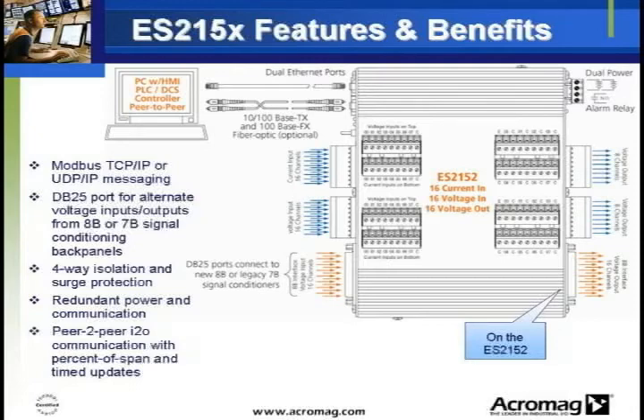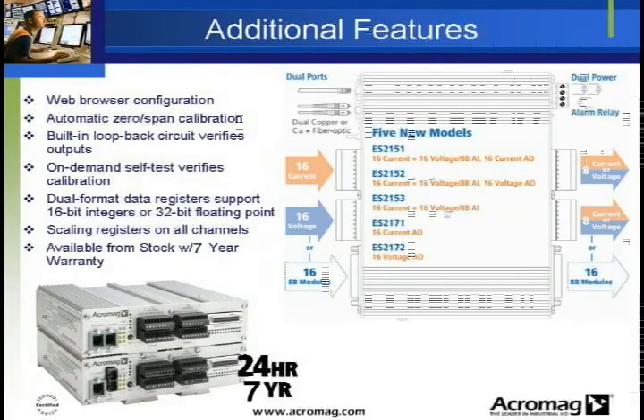Redundant power and communication ports provide bumpless switching to keep the data flowing if a line breaks or if a power supply gives out. And Acromag's peer-to-peer I2O communication now supports percent of span and timed updates for fast and efficient transmission of data. Additional benefits of the EtherStax units include a web-based configuration interface so that there is no need to install any software. Only your web browser is needed, so configuration is easy and compatible with any operating system.